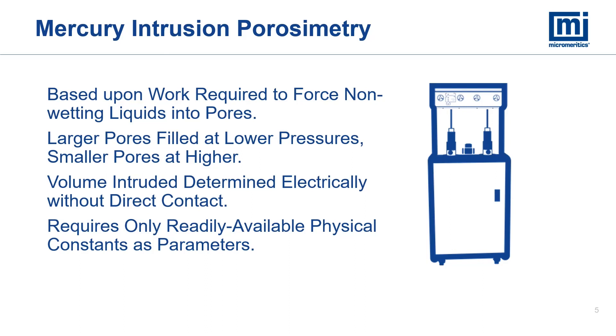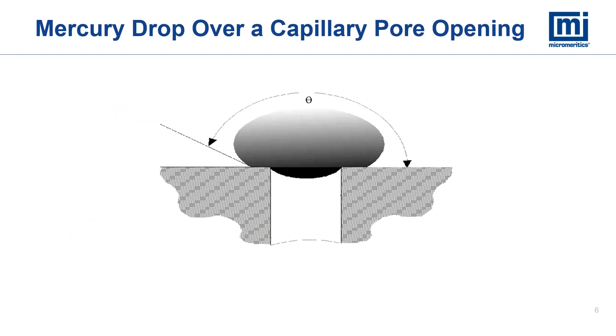Mercury intrusion porosimetry is based upon the work required to force a non-wetting liquid into open pores. Both dead-end pores and through pores are characterized, with the volume of pore filling through the opening to the pore recorded along with the pressure at which the pore fills. The work is necessary to extend the surface area of the mercury down into the pore against the surface tension of the liquid mercury. Since larger pores have less surface area as a function of their volume, it is easier to force mercury into larger pores at lower pressures than into smaller pores, which require higher pressures. The intrusion volume is determined electrically using capacitance, and only a few physical constants are needed.